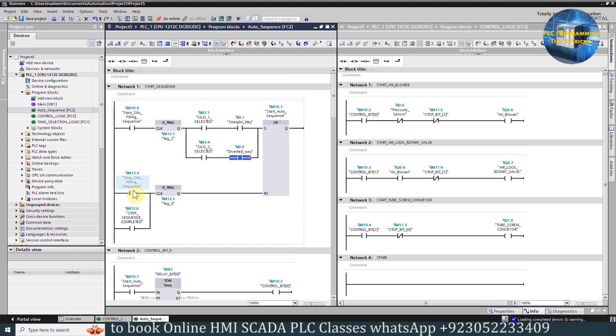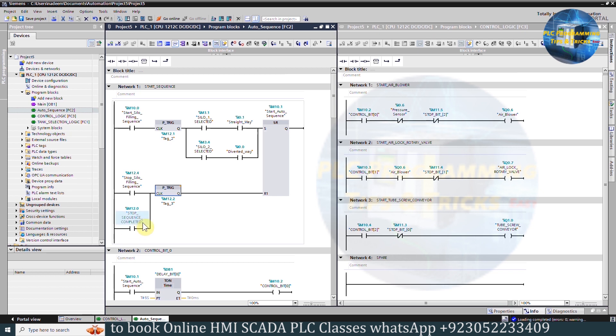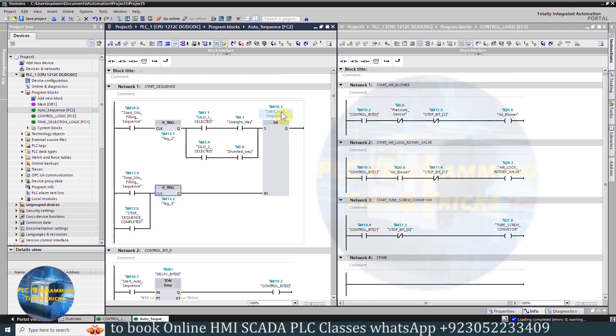When we turn on the stop-silo filling sequence bit, on the rising edge it will reset the start-sequence bit M10.1. Similarly, on the rising edge of the stop-sequence completed bit M12.0, it will also reset the start-sequence bit M10.1.